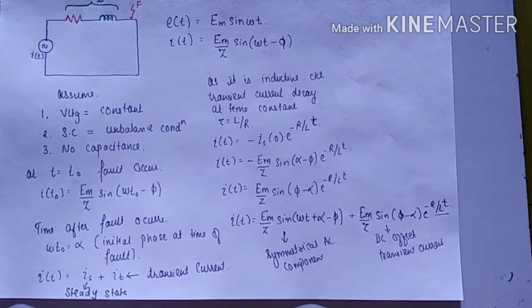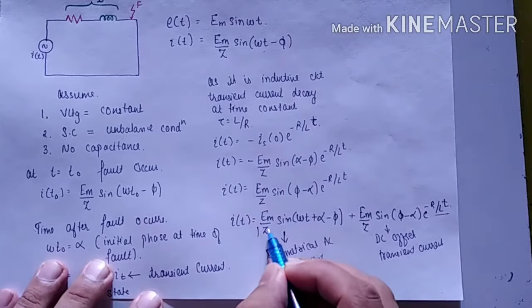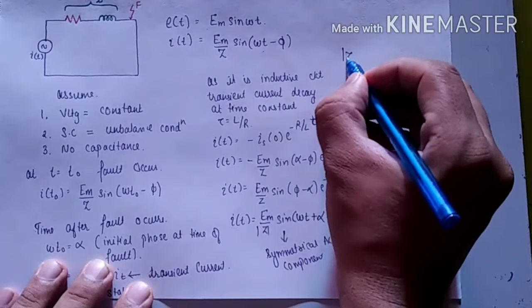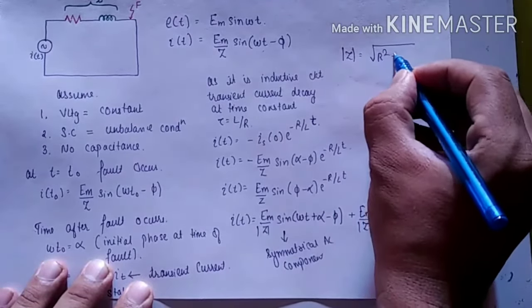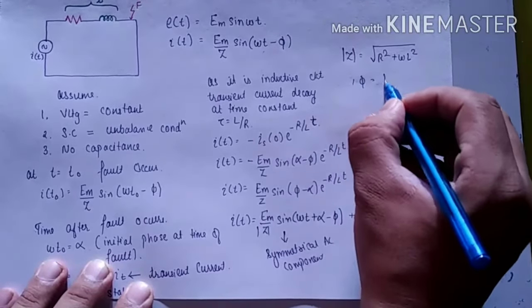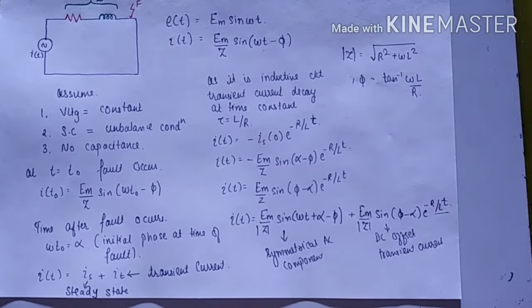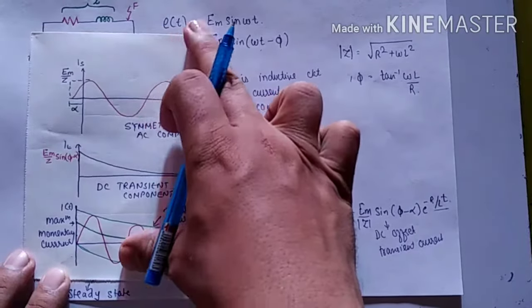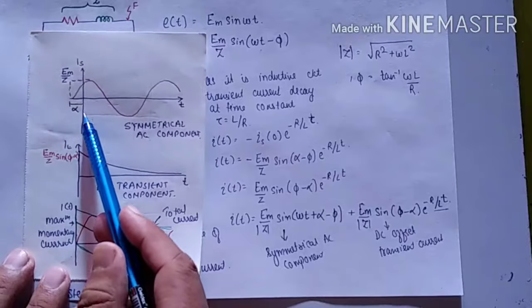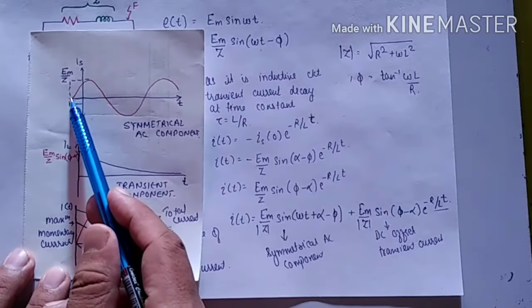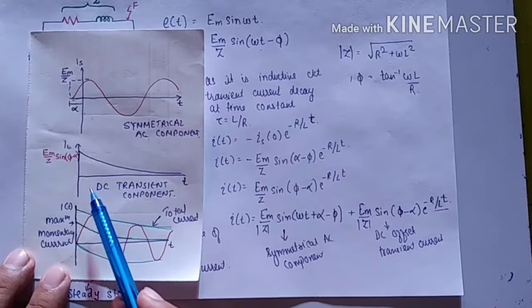The total current is Is + It. We also know that Z = √(R² + ωL²) and φ = tan⁻¹(ωL/R). The graphical expression shows the symmetrical AC component, with α indicating the angle at which the fault occurs.